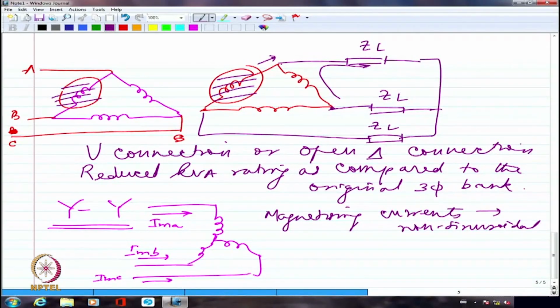We call these harmonic components: second harmonic, third harmonic, fourth harmonic, fifth harmonic, and so on. So this non-sinusoidal magnetizing waveform gets decomposed into 50 hertz, 100 hertz, 150 hertz, and so on. As the harmonic order increases—5th, 7th, 9th—each becomes smaller compared to the fundamental, since the primary waveform corresponds to 50 hertz. So as you go to higher order harmonics, the magnitude generally decreases proportionately.